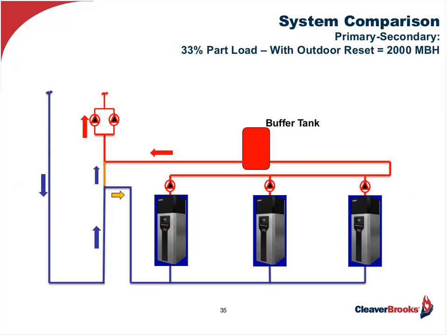Now let's take it down finally, one other scenario, down to 33% load, and with outdoor air reset. So now we're down to 140 going out and 100 coming back, 100 GPM on the system. I'm going to run 2 boilers to make sure I don't have any reverse flow in that decoupler. This is also one of the toughest things in controlling a primary-secondary loop, when you stage your boilers, because of course the system doesn't sit at 33% all the time. It's going to be moving around. It's dynamic. And you don't want to be cycling the boilers too fast.